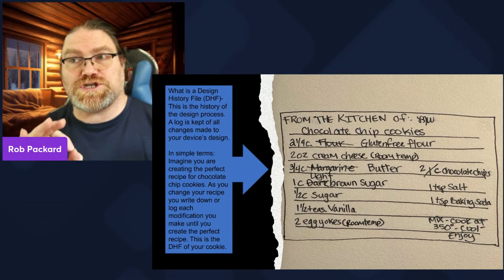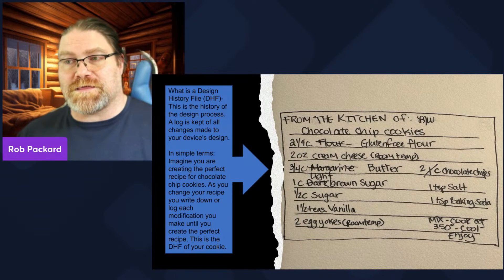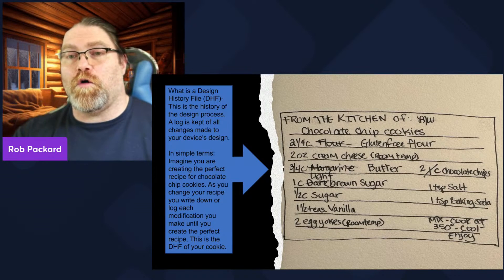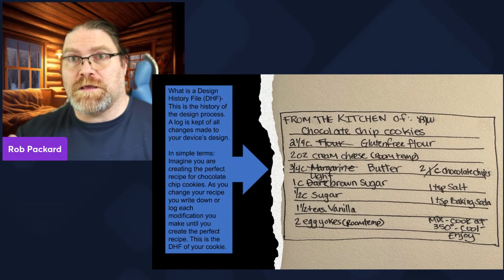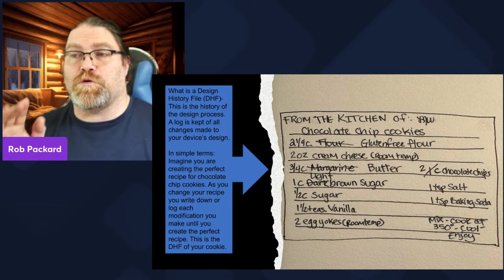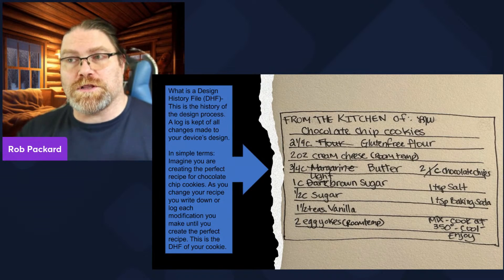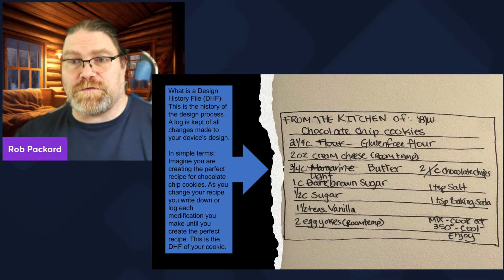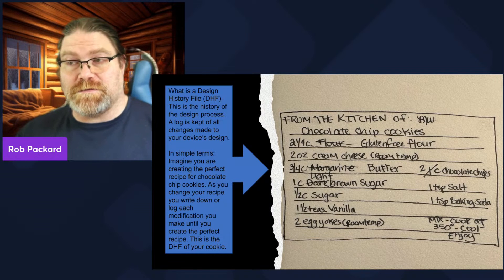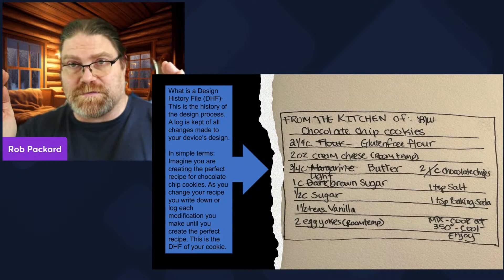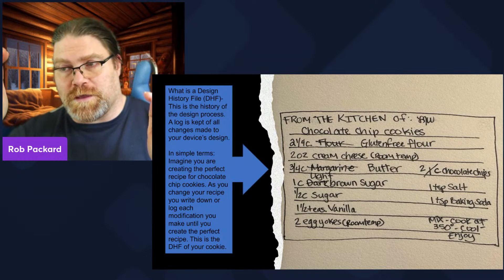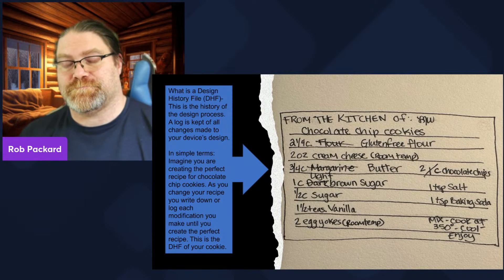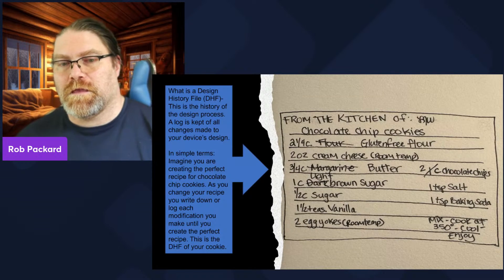The DHF is the history of all the things you've done from the beginning of time until you launch the product. We don't keep the design history file open after we release the product. Once you have a 510k, we close the design history file. Why? Because only the FDA cares about the design history file — everybody else just wants records of design. The FDA calls it the design history file from beginning to end, and they want it closed when you have a 510k. If you make changes after that, that's a new design history file.